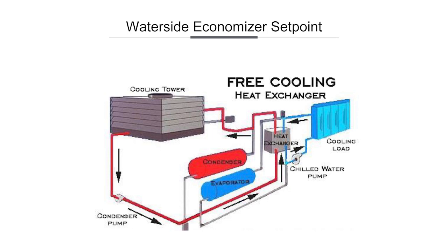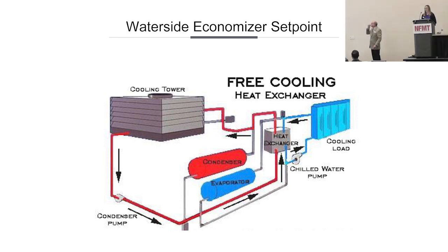So for this setup, the supply temperature that was supposed to be going to the building was actually 40 degrees. We know that's very low typically. For this building, it was serving lab spaces, so we had to have it that cold. With that being said, the water that was supposed to be going into the heat exchanger, or coming out of the heat exchanger, had to be 36 degrees.